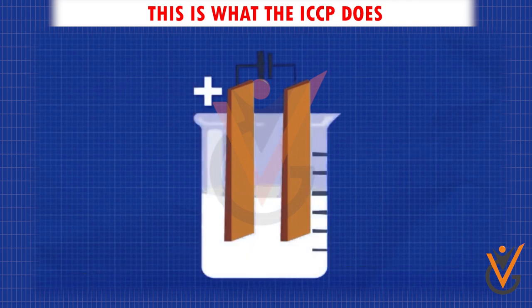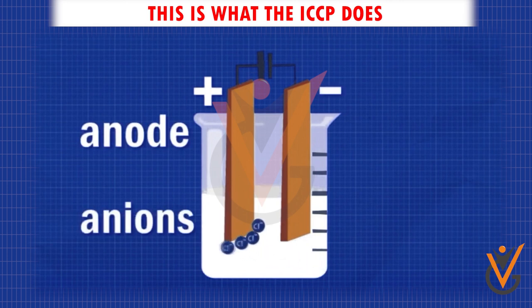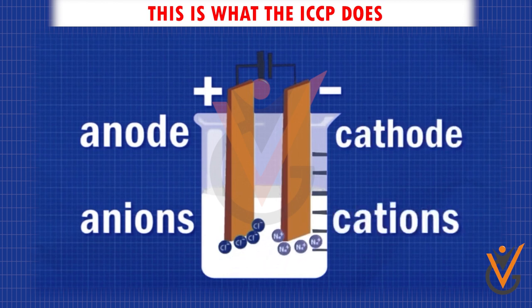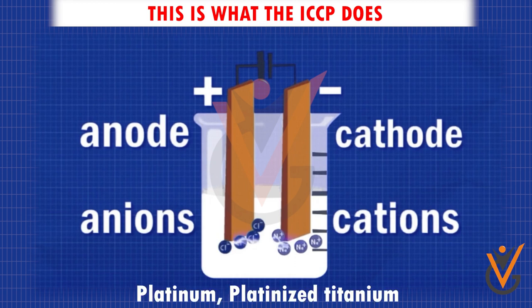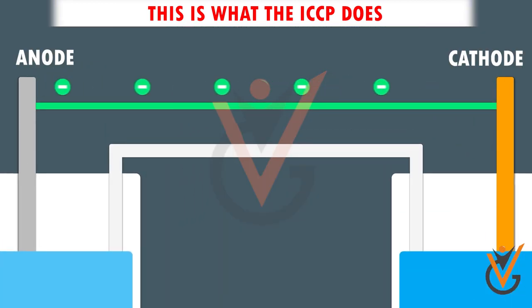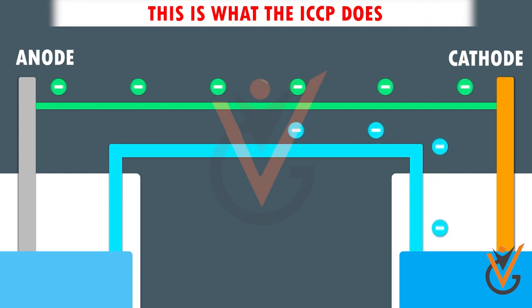In the ICCP, the metal to be protected is connected to an insoluble anode, and the current is passed using a DC source opposite to the corrosion current, so that the corroding metal gets converted from anode to cathode and is protected from corrosion. This insoluble anode can be either platinum, platinized titanium, or any other inert elements. This DC current has to be equal to or slightly greater than the natural corrosion current so that the anode is now protected and does not corrode.